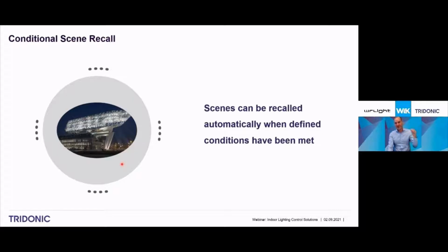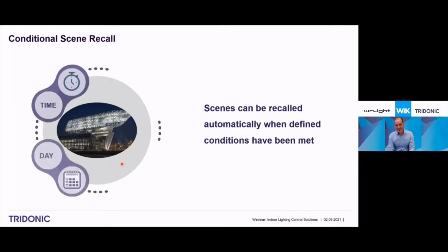You create, for example, a scene where you say 50% light level, 100% light level, and then define in the system, for example, an office space with multiple single offices but one central corridor. With combinations and conditions, you can say, based on the time or the day of the week, when there is still presence detected in one of the single offices on that floor, the corridor should always have a light on.